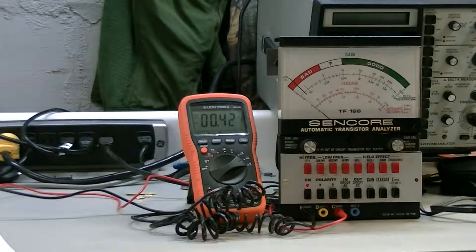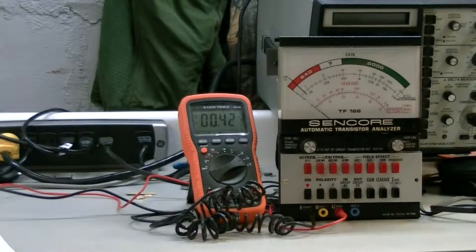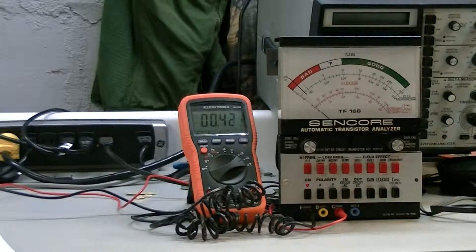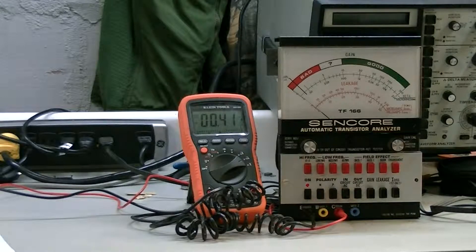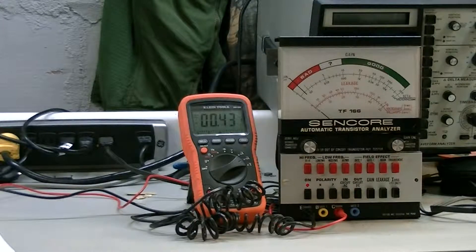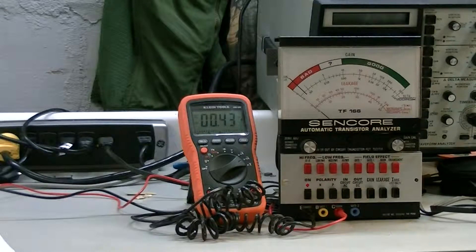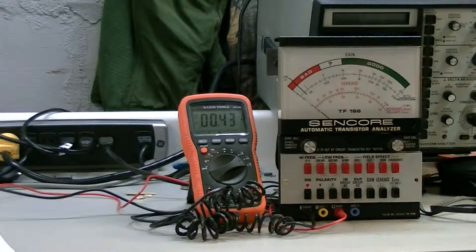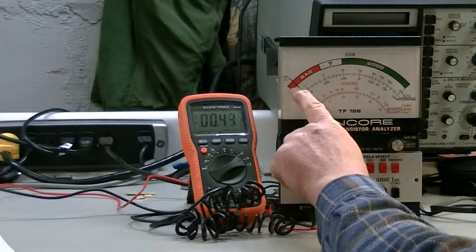So I'm going to go through the calibration instructions here. It tells you to remove the TF166 from its case, which is done, and then you're supposed to lay it on its right side and adjust the static meter zero to zero on the left edge.